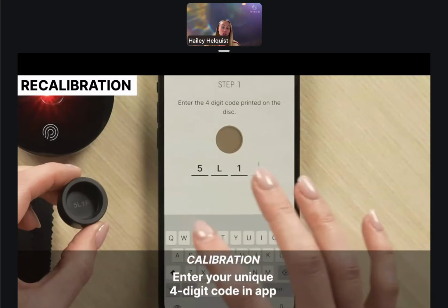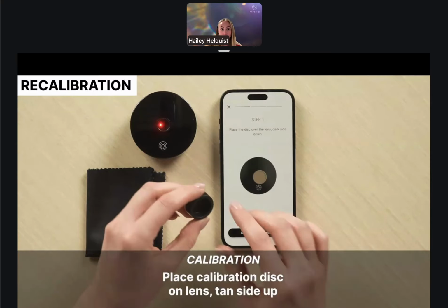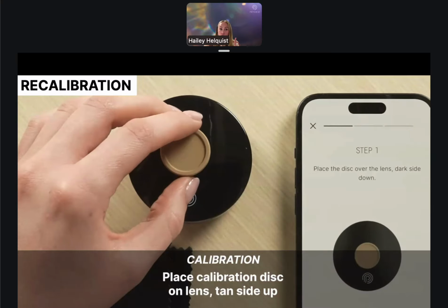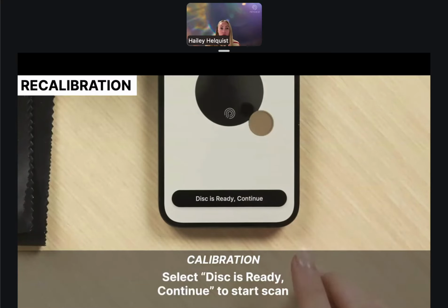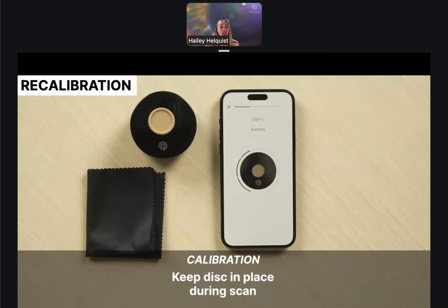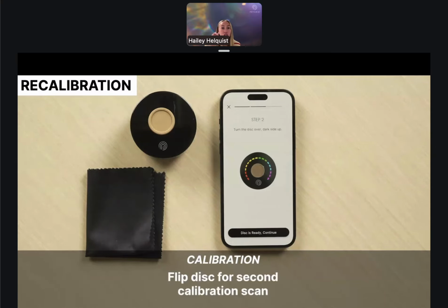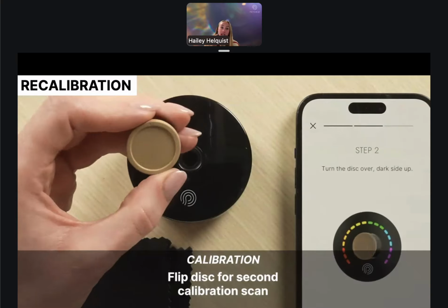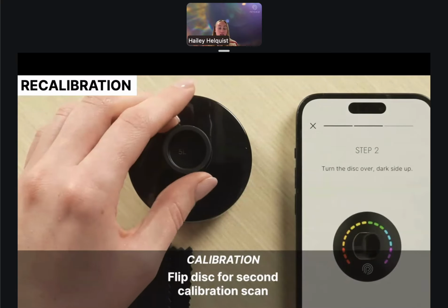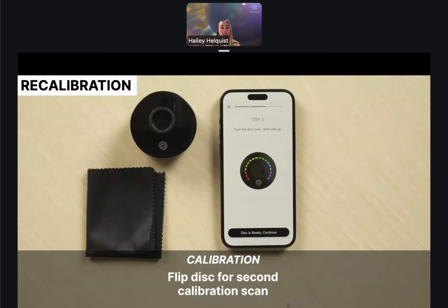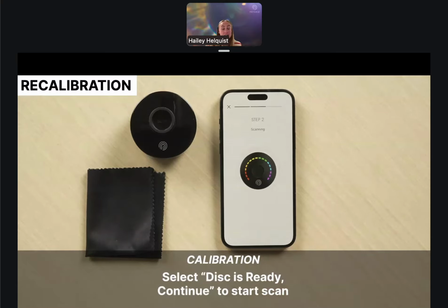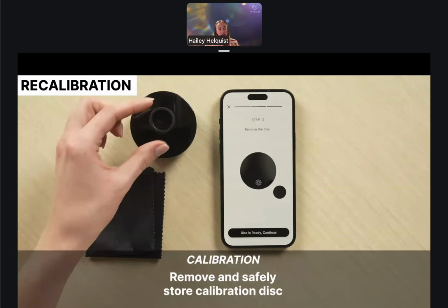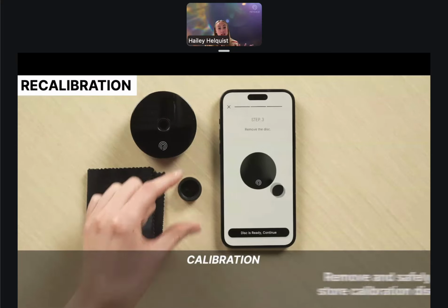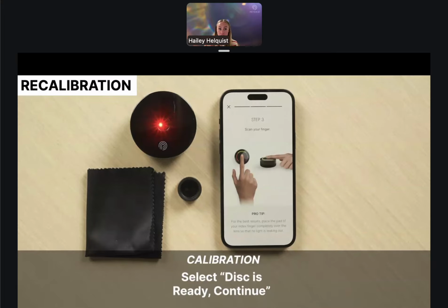But again, some things to keep in mind, especially when you recalibrate the device: one, make sure that you use that microfiber cloth on the lens before you calibrate. And two, make sure that the calibration disc is clean as well. If you're putting it in your pocket or in the bottom of your purse or your bag, that disc can attract lint and maybe other dust, and that can impact your calibration as well. So best practice is to keep it in your travel case. Keep that calibration disc in there and the device in there to help make sure that both are staying clean and protected.